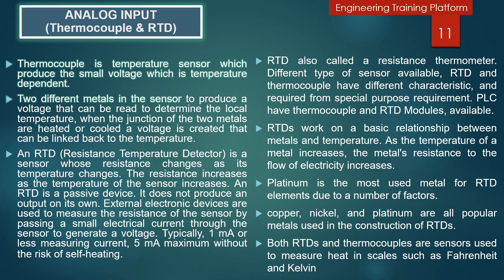RTDs are superior to thermocouples in that their readings are more accurate and more repeatable. Repeatable means that measuring the same temperature produces the same result over multiple trials. RTDs producing more repeatable readings means their readings are more stable, and their design ensures that RTDs continue producing stable readings longer than thermocouples. Furthermore, RTDs receive cleaner signals and are easier to calibrate. Both RTDs and thermocouples are sensors used to measure heat in scales such as Fahrenheit and Kelvin. In general, thermocouples are cheaper, more durable, and can measure a bigger range of temperatures, while RTDs produce better and more reliable measurements.